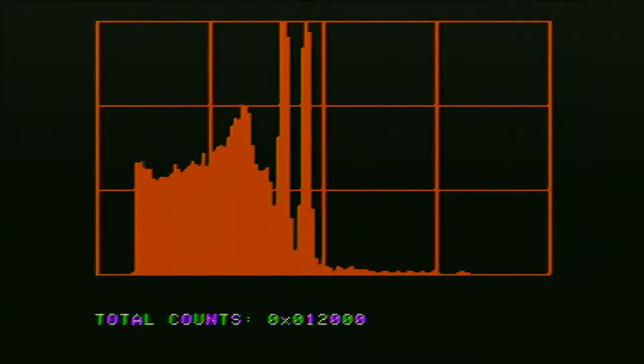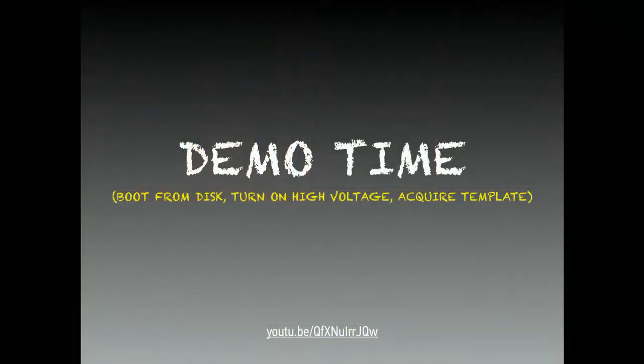Yeah, so let's go back to the main screen. If we let this run in the background, we come back to this after a while. Probably Alex actually has to push a button on the computer to acquire. There's one issue - the detector has to warm up a little bit, so ideally we'd have to wait 5 minutes or so to stabilize the high voltage. So we'll see how we'll be doing on the verification or the inspection in a few minutes.